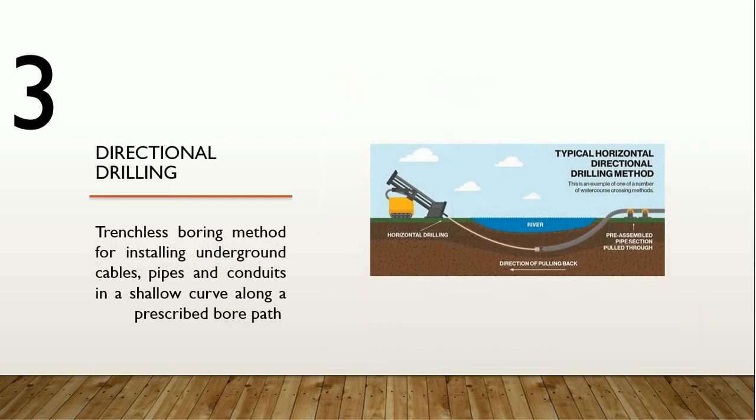The third type is directional drilling, a trenchless boring method for installing underground cable or pipes in a shallow curve along a prescribed bore path. There will be a sending bit and receiving bit. The machine will dig from sending to receiving and pull the cable to the other side.